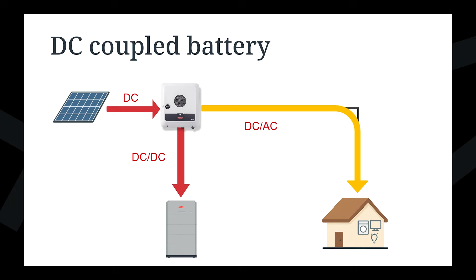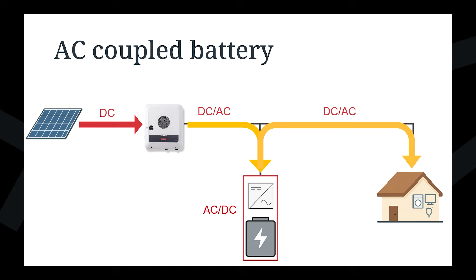Now, with an AC coupled battery, that's not directly connected to the inverter. It's on the AC side of the system, okay? Now, the panels are producing DC, as we know. The inverter will put out AC power, okay? And then this AC coupled battery has its own little inverter in it. That's what's drawn there. That's an inverter symbol. So that's there because it's going to take that AC power in, and then it'll be able to convert it to DC power, which is how the battery is going to store it, right? So the AC coupled battery means it can only accept AC power to charge it. And then, yeah, it stores it as DC power. And then when you want to use it, it's essentially going to be converted back into AC power to be sent to the loads.